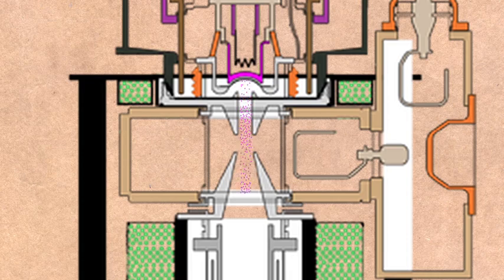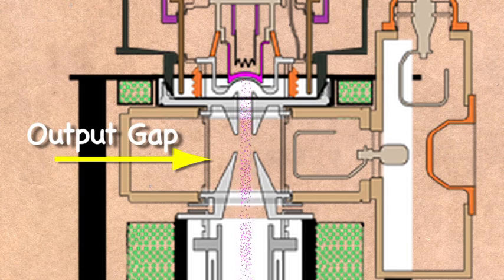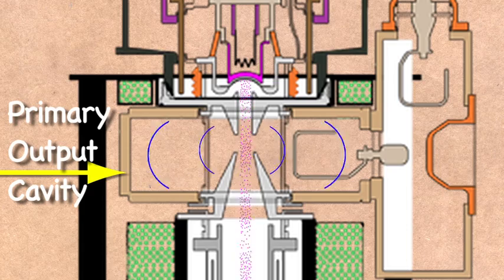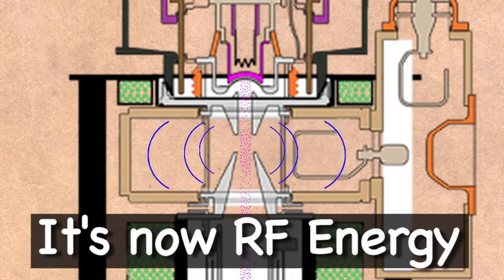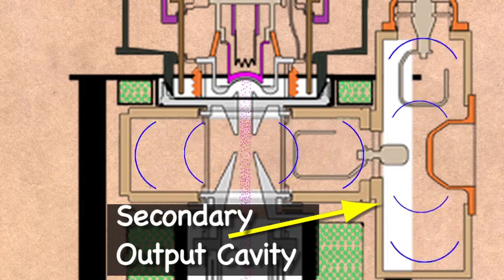As the density modulated beam of electrons flows down through the body of the IOT, they pass the output gap of the tube. This is where the primary output cavity is located. The modulated beam of electrons interact with this resonantly tuned cavity, and a probe intercepts this energy, and transfers it to the secondary output cavity.